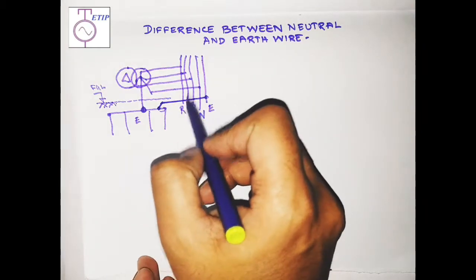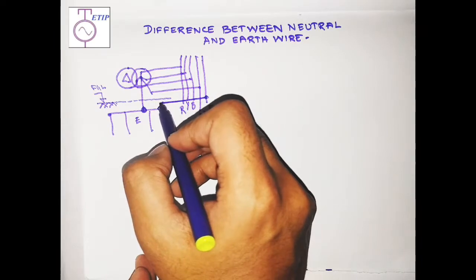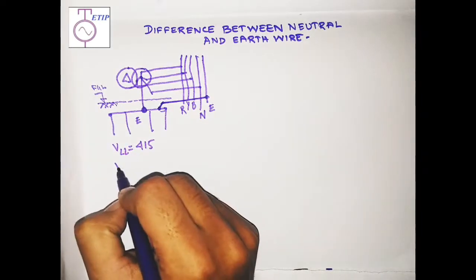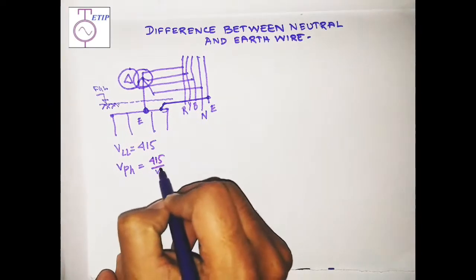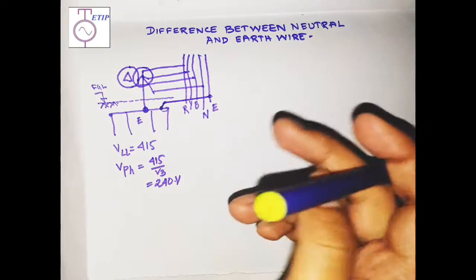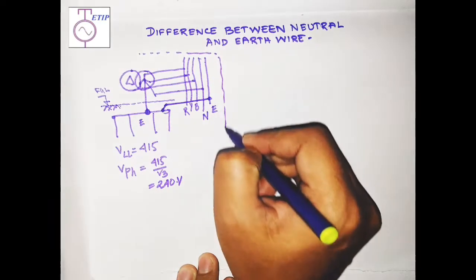From the transformer in the substation switchgear there is three phase, one neutral, and one earth. This neutral is only used in the 415 volt system to draw single phase supply. Line-to-line voltage is 415 volt; when drawing single phase we take line and neutral, giving the phase voltage of 415 divided by root 3, which is around 240 volt. For higher voltage levels like 11 kV or 6.6 kV, only three-phase line-to-line voltages are used.